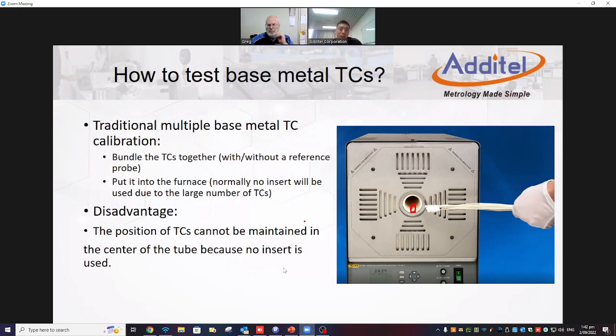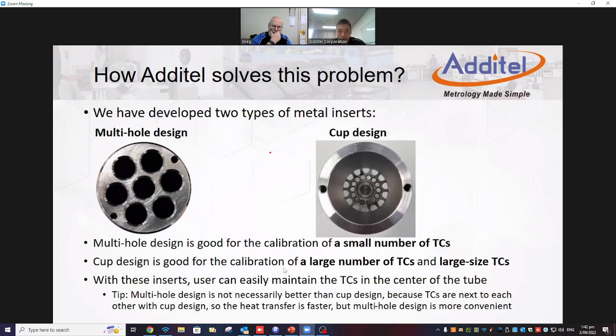So this is the traditional way. To overcome this problem, we have a special cup design, or we can say the multi-hole design. That's the insert. You can see the multi-hole design like this. This is pretty good for customers who only need to test a few thermocouples at one time. They put the reference probe in the middle, and for the other DUT tests, they can put them in the other holes like this, and then put this insert into the core of the furnace.